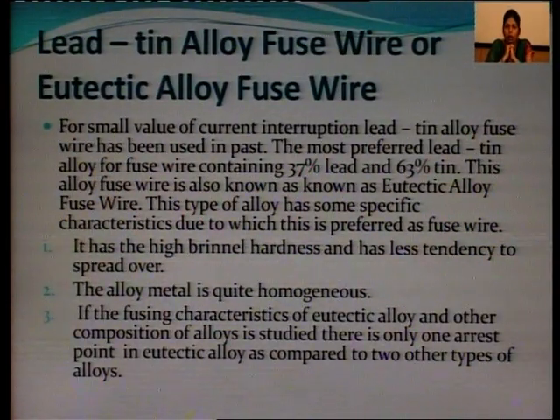The next is lead tin alloy fuse wire, used for small values of current interruption. Lead tin alloy fuse wire has been used in the past. The most preferred lead tin alloy for fuse wire contains 37% lead and 63% tin. So we use an alloy of lead and tin in this ratio, and this alloy fuse wire is also known as eutectic alloy fuse wire. This type of alloy has some specific characteristics due to which it is preferred as fuse wire.